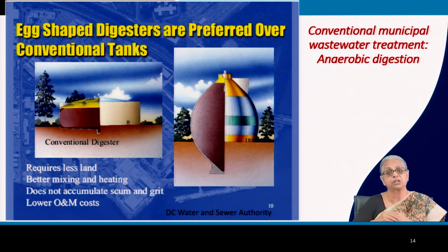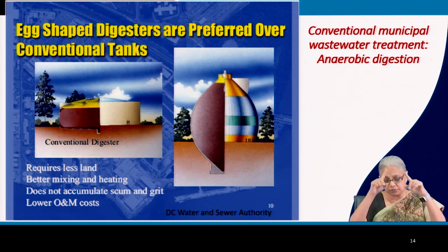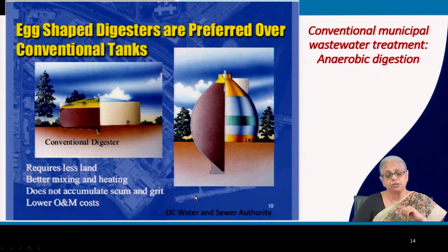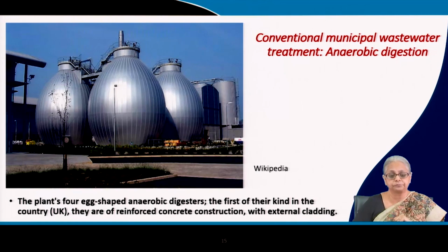Now in egg-shaped digesters, I have been told, again, that because of the nature of the digester, the egg shape, you don't need to do any cleaning. Absolutely no cleaning has been done in this particular case, and you get good results in terms of biogas generation.